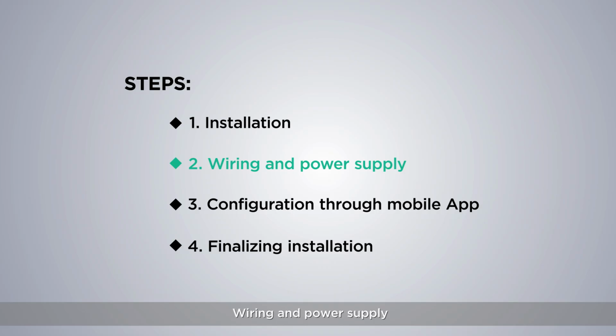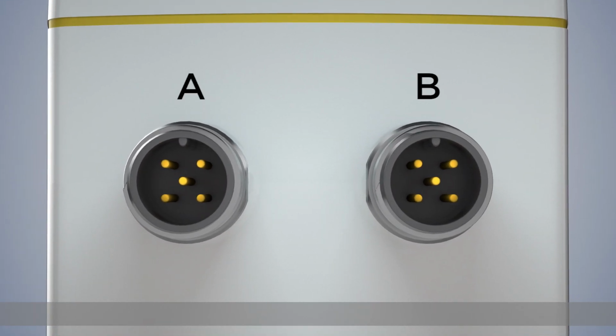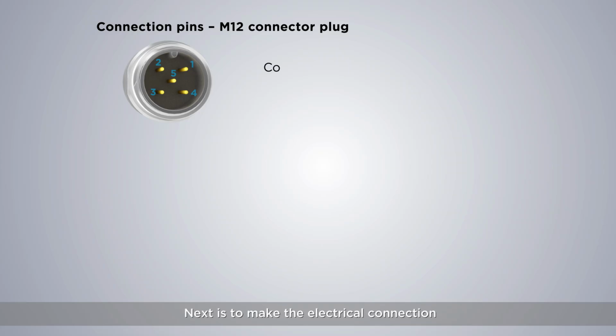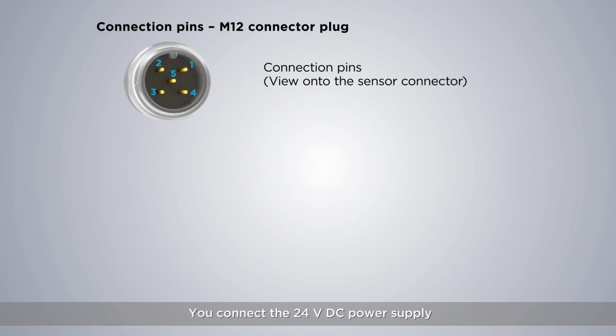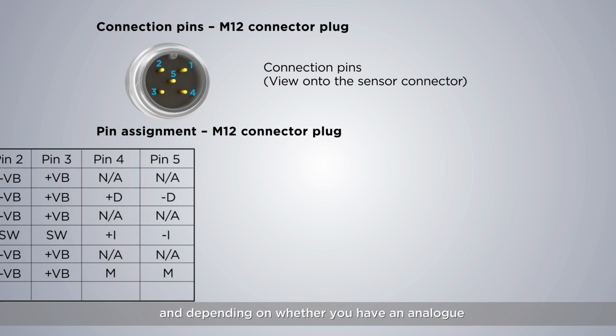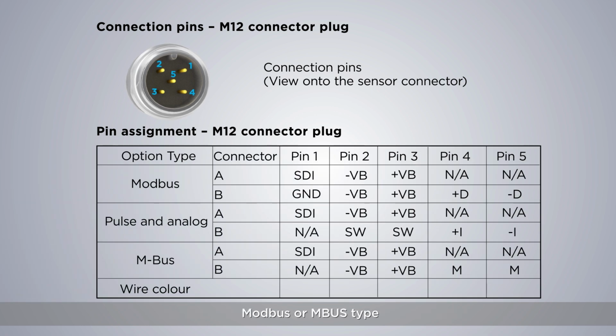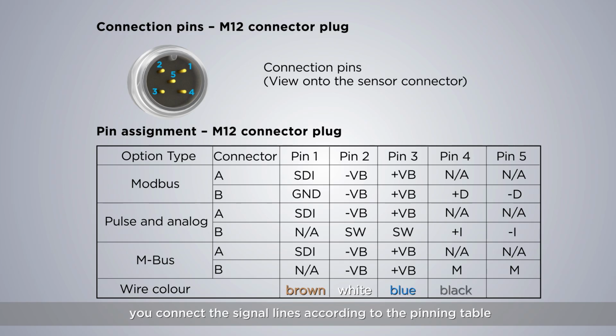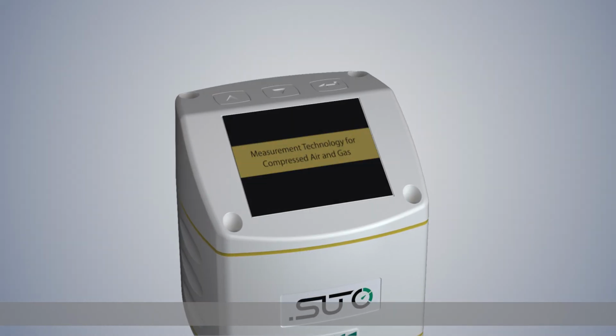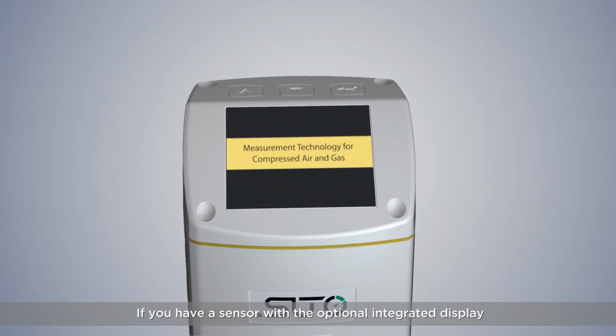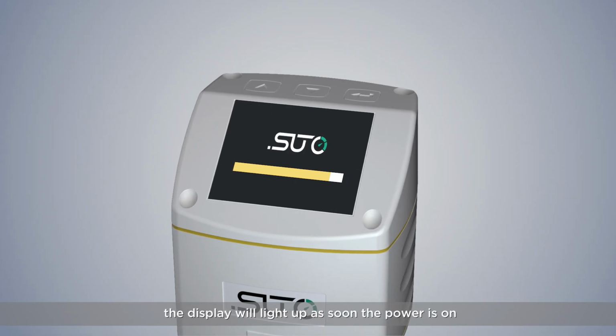Wiring and power supply. Next is to make the electrical connection. You connect the 24-volt DC power supply and, depending on whether you have an analog, Modbus or M-bus type, you connect the signal lines according to the pinning table. If you have ordered the sensors with the sensor cables, you can use the color codes to connect the signals to the right terminals at the monitoring system, which can be a PLC or any remote terminal unit. If you have a sensor with the optional integrated display, the display will light up as soon as the power is on.